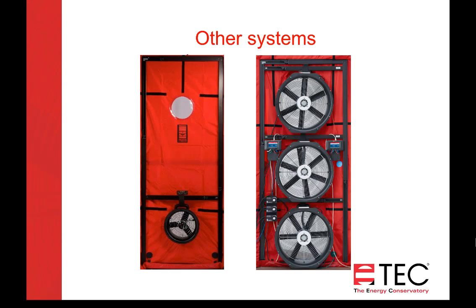And we're using 2 DG1000s for 3 fans because in the software you can set up the way this one's set up. The gauge on the left is set up like you would for a regular blower door test with the lower fan, so the lower fan flow and the outdoor reference pressure. And then the middle fan and the upper fan you can read out from the gauge on the right, because the software allows you to set it up that way.